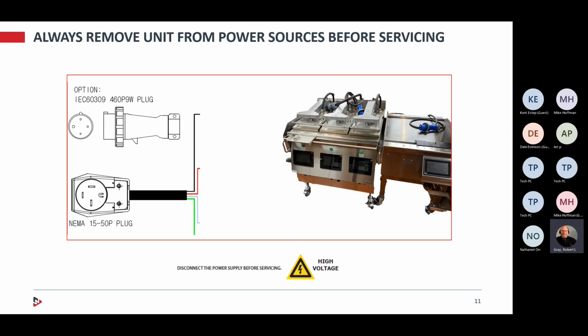And the reason I say that is before you open up a side panel or a front panel, you don't want to accidentally drop that panel inside the unit and arc it like I did a few months ago when I was out at a location. Somebody bumped me, I dropped the panel, it went down on top of a contactor, and it arced out. Luckily, nobody was hurt. Yeah, I had to replace a couple components, but that's unfortunate. It shouldn't have happened if I would have unplugged it first.